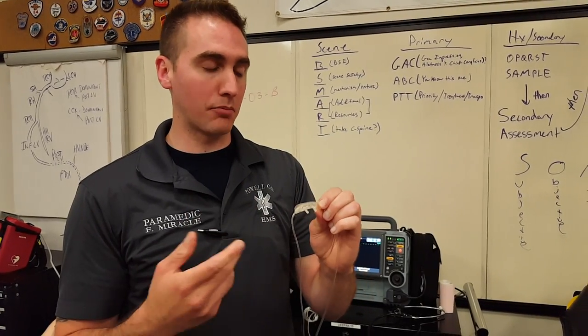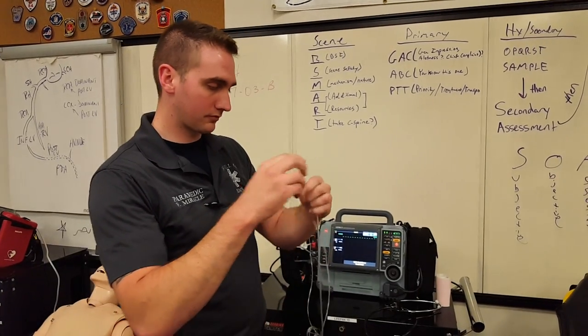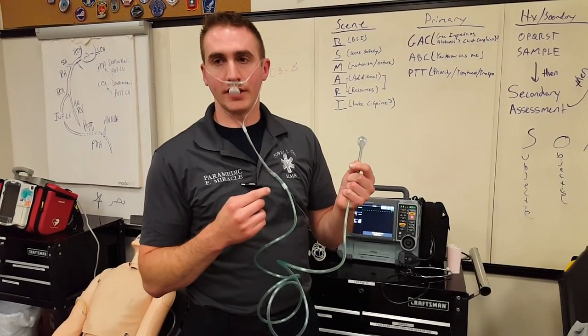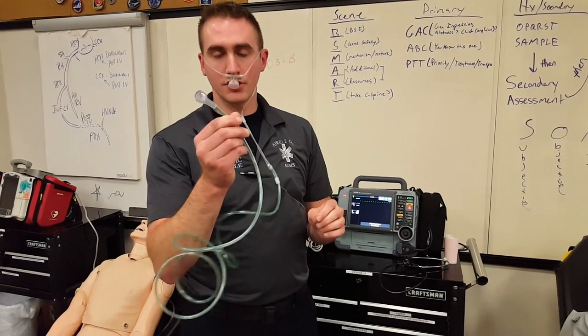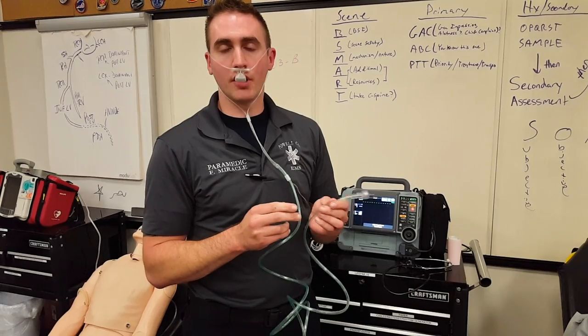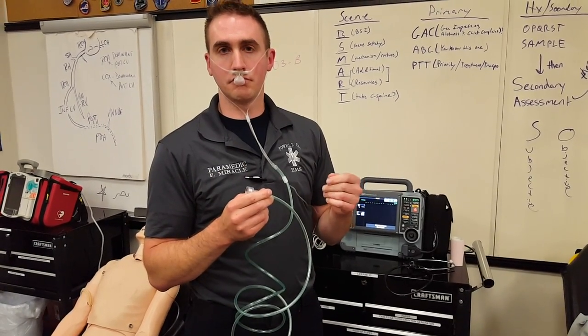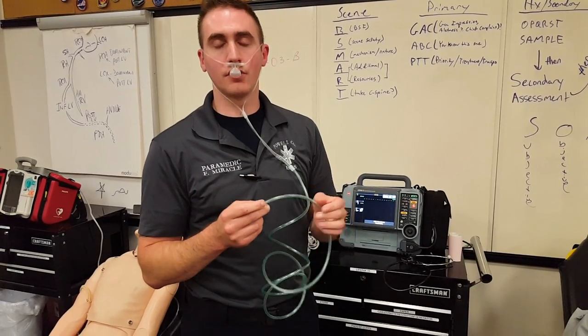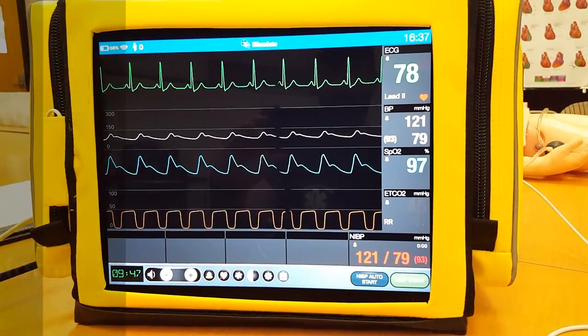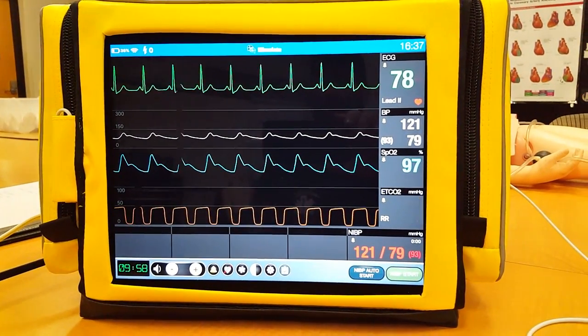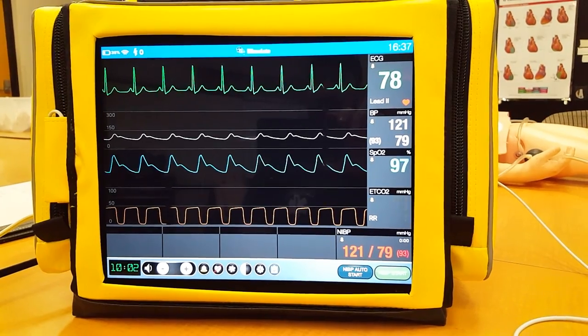If you increase the oxygen above two or three liters per minute, you're actually going to decrease the accuracy of your end tidal CO2 measurement — you will wash out some CO2 the patient is exhaling, giving you a falsely low measurement. Some sidestream nasal cannulas come with the oxygen tubing already connected, while others require a separate supply tubing to be connected. Now let's break down the normal end tidal CO2 waveform and talk about a couple of key variations, with more detailed waveform explanations to follow in future videos.